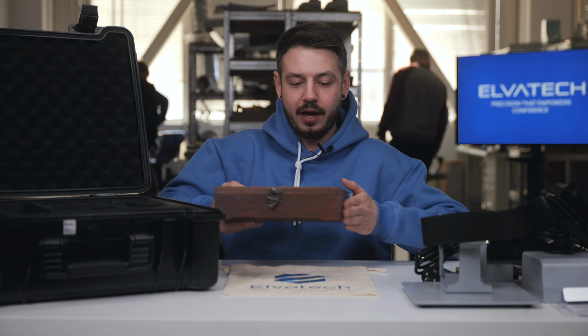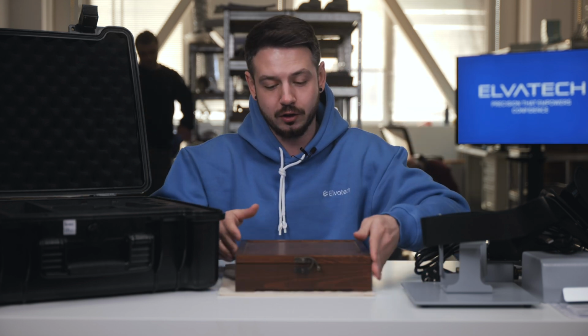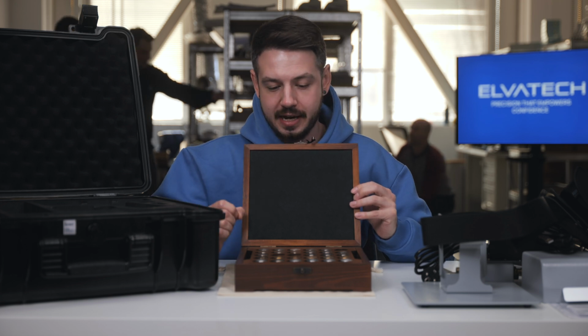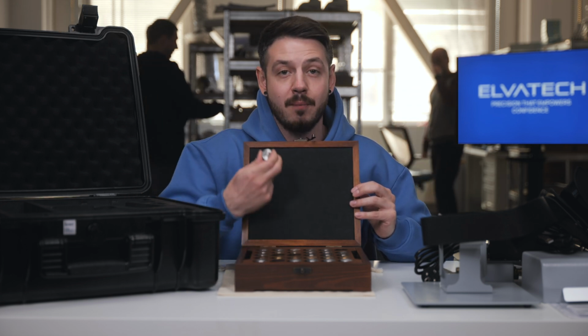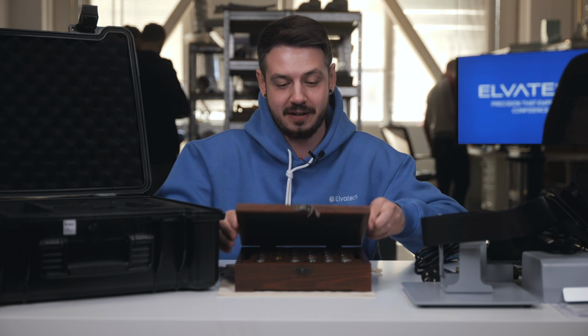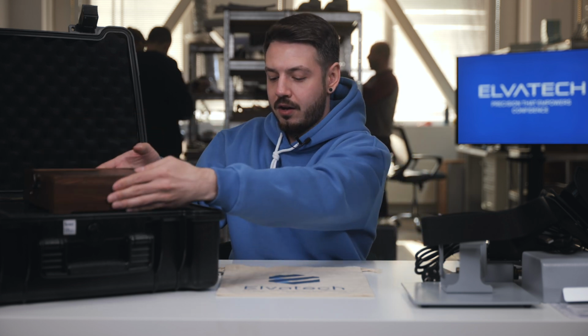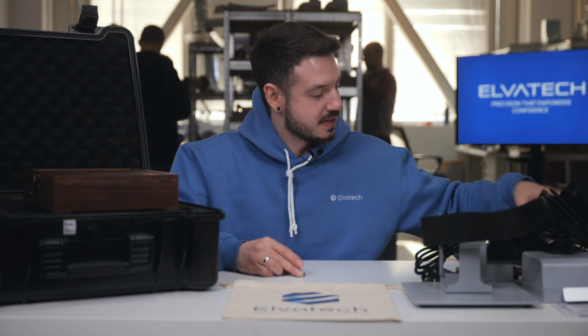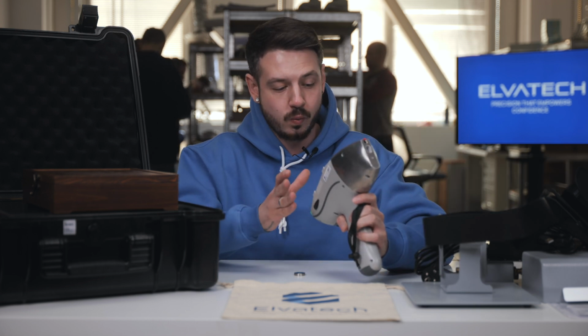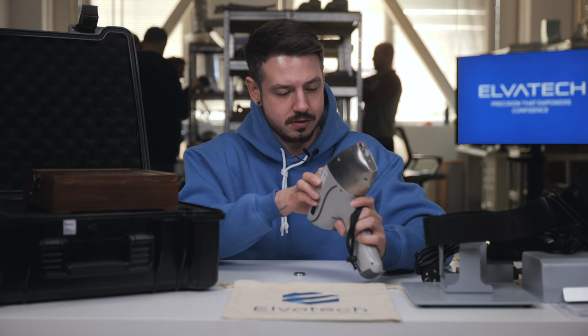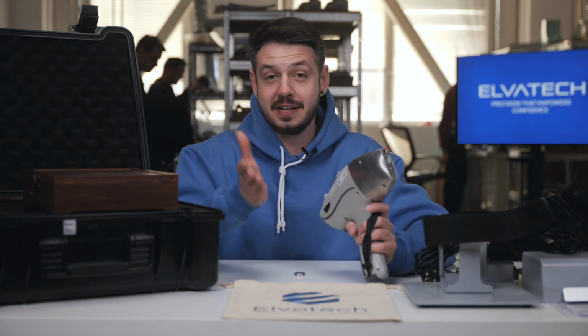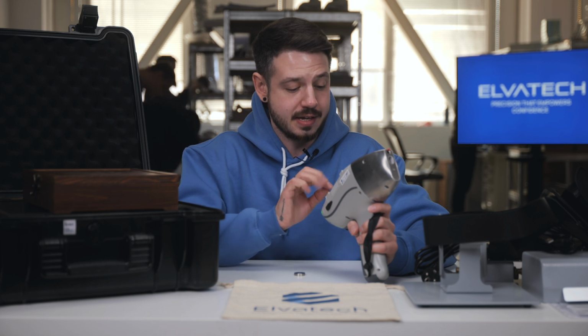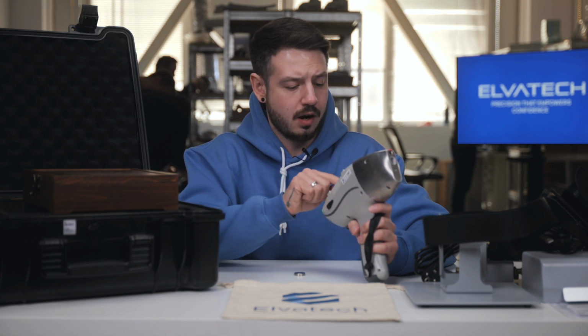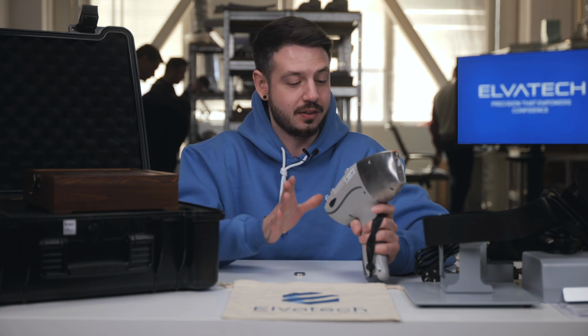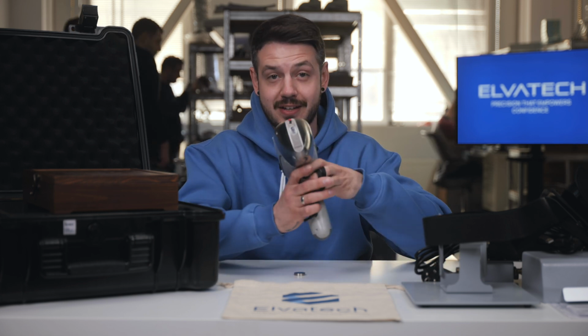Well, we have the special alloy base box here with different alloys and different alloys grade. So let's take, for example, the simplest, it's RM316. So basically this is the grade of 316, right? Also, all we need to do is take our device and switch the right calibration. For this one, we have alloys without light elements. All right, head into calibration, and we need to set our necessary settings just to ensure that the duration is correct, because we will select just for 5 seconds. It would be absolutely enough to check this alloy.